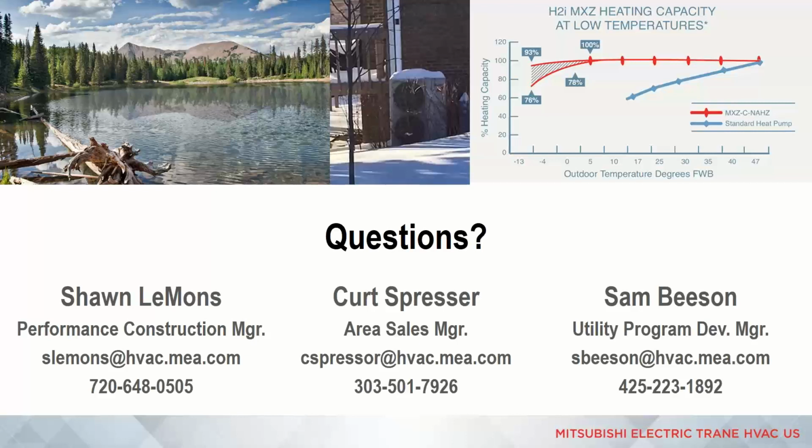Right, so the question, do they work with baseboard and radiant in-floor? I will say this, the cold climate heat pumps are a standalone solution in many cases, many applications. If someone already has a system that they want to keep as a backup or use as a supplemental source, whether it be electric or another fuel, there are different indoor units that can monitor the condition of the air coming back into them, what we call the return air. It knows where it is, it knows where it needs to be, and it's checking to see how quickly it can get there over time. And if it sees that it can't keep up, it can call for additional heat. So if I understood the question correctly, there is a way to connect our cold climate heat pumps with those other units for a more robust and complete system.